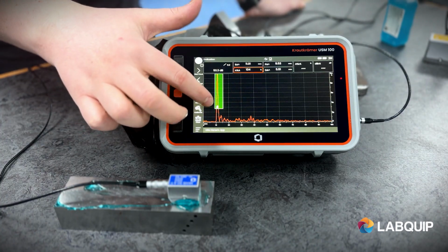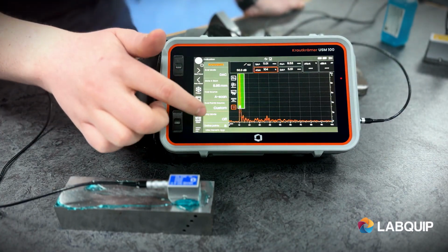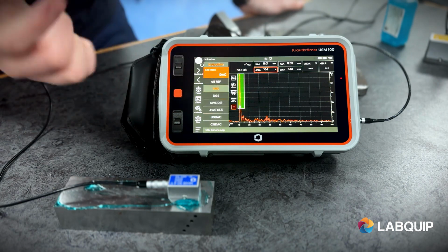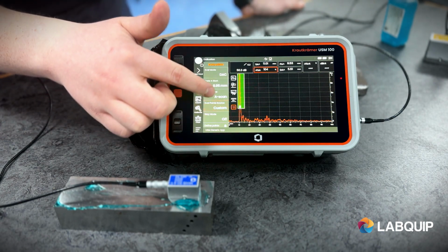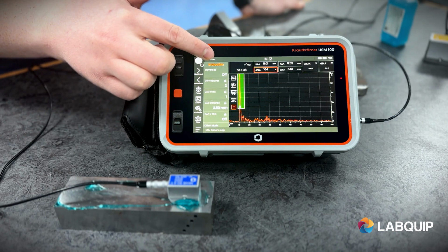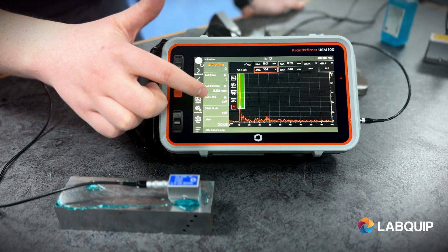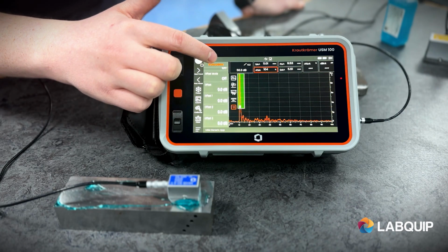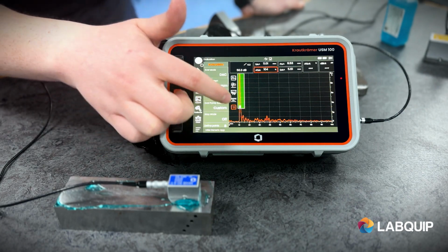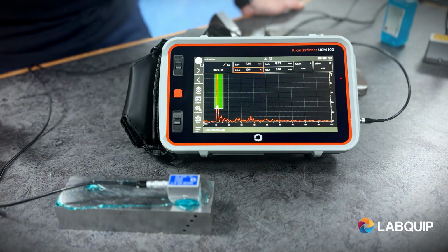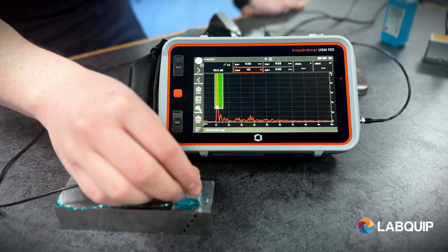Now before we do that, we can go in and tell it what type we want to do. So eval mode, DAC, DGS, whatever you need it to be. And you can adjust your gates, define your points, things like this. But we're all set up here and ready to go. We'll do our offsets and everything at the end. It's automatically already set to go.